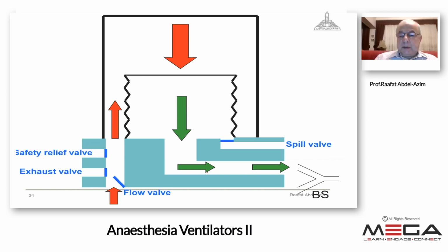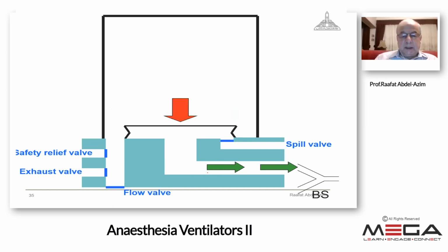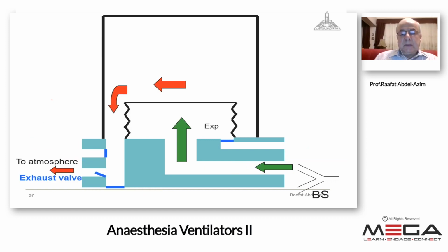This is the situation of the mid-inspiration. This is the end of inspiration. The flow valve will be closed and all other valves are also closed. After that, the patient's lung will be allowed to deflate and the bellows will come upwards containing the patient's gas or the expired gas. When it goes up, the driving gas inside the chamber should be vented, and this will be done through the exhaust valve, which opens throughout the expiratory time, venting the driving gas into the atmosphere.